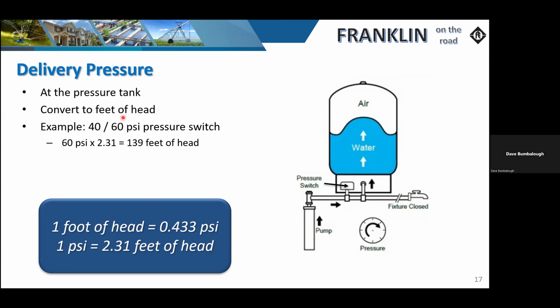Okay, so we're going to convert that. Since most of what our calculations consist of is basically lift or total dynamic head, we're going to convert to feet of head by doing this simple calculation. We're going to take 60 psi times 2.31, which is equivalent to 139 feet of head. Now, in my exercises, I always round that up, so I'm going to use that as 140. I don't mind rounding up just a little. You don't want to overshoot too much because that drives the horsepower up. And as I go through this, you'll see why that's a bad thing.